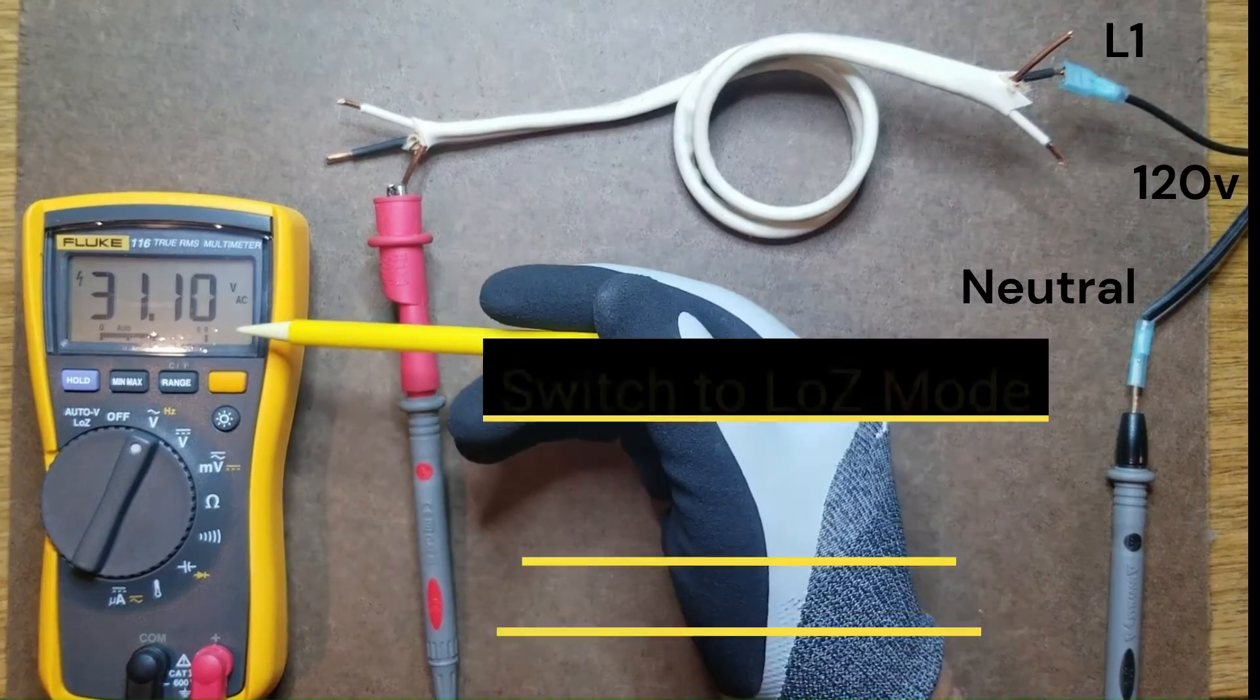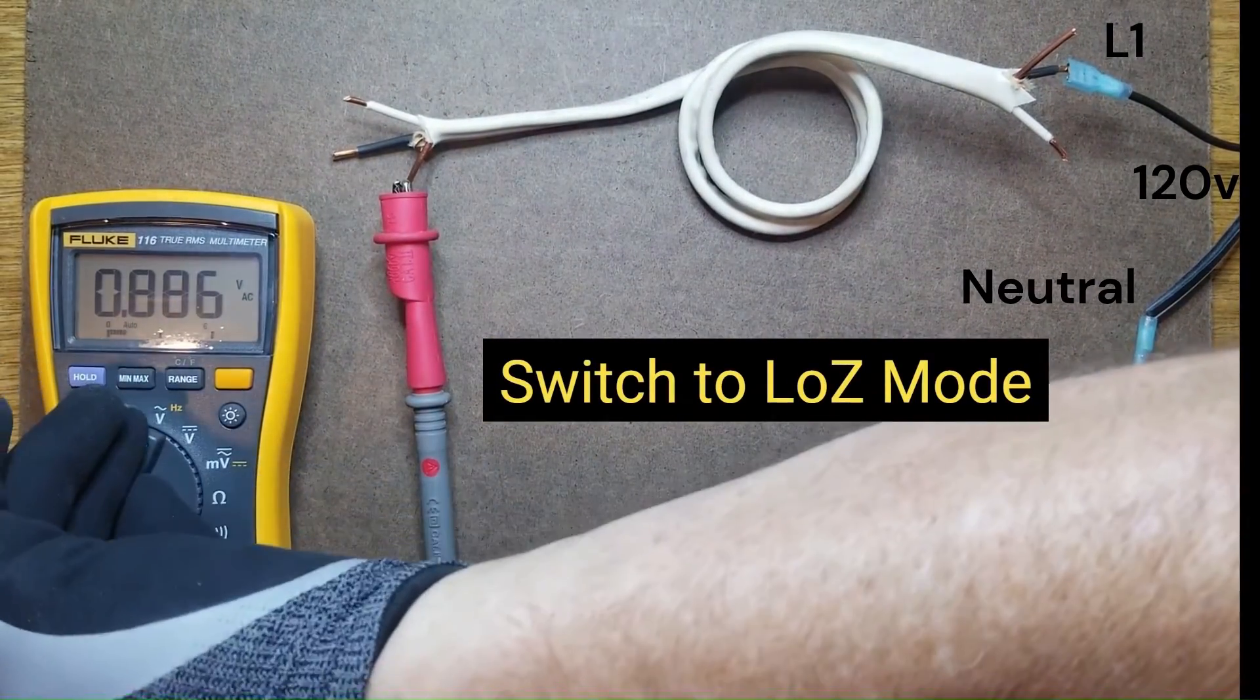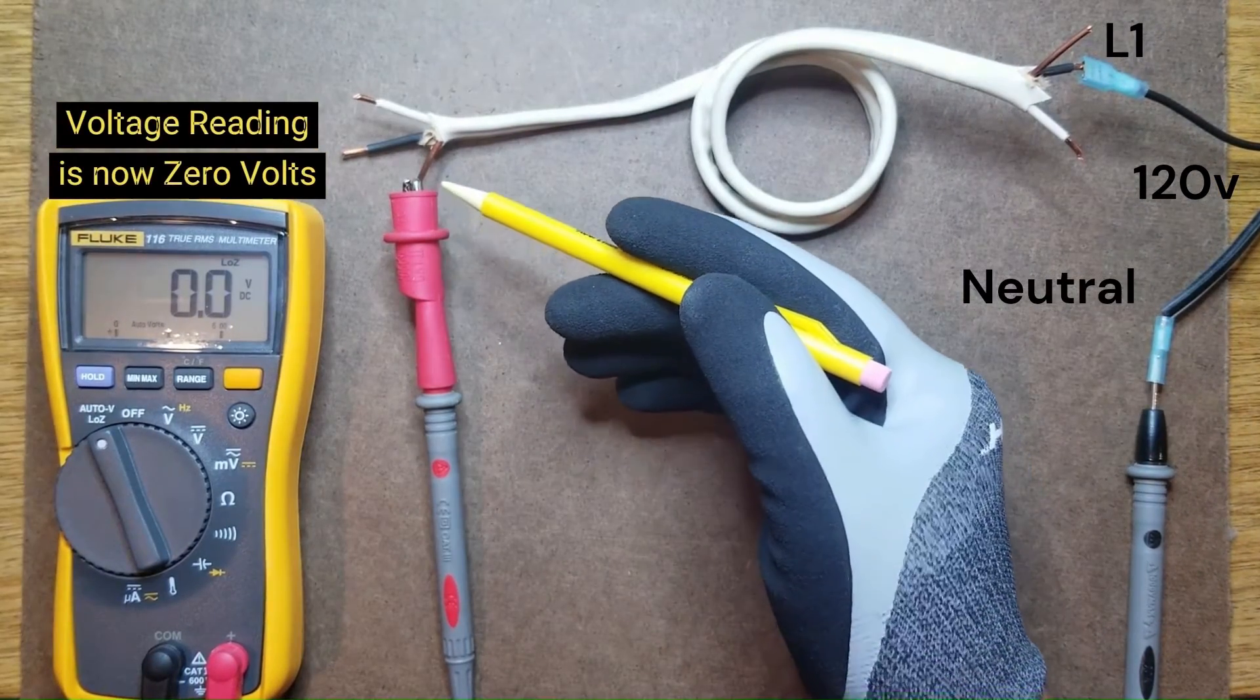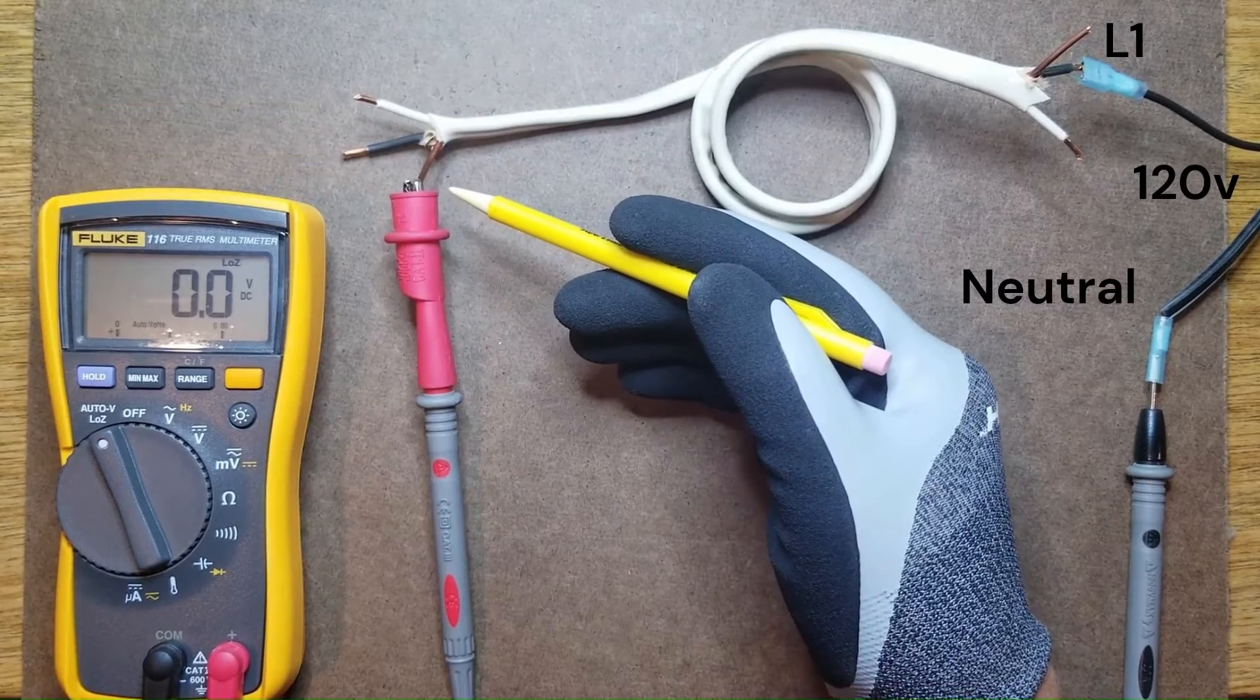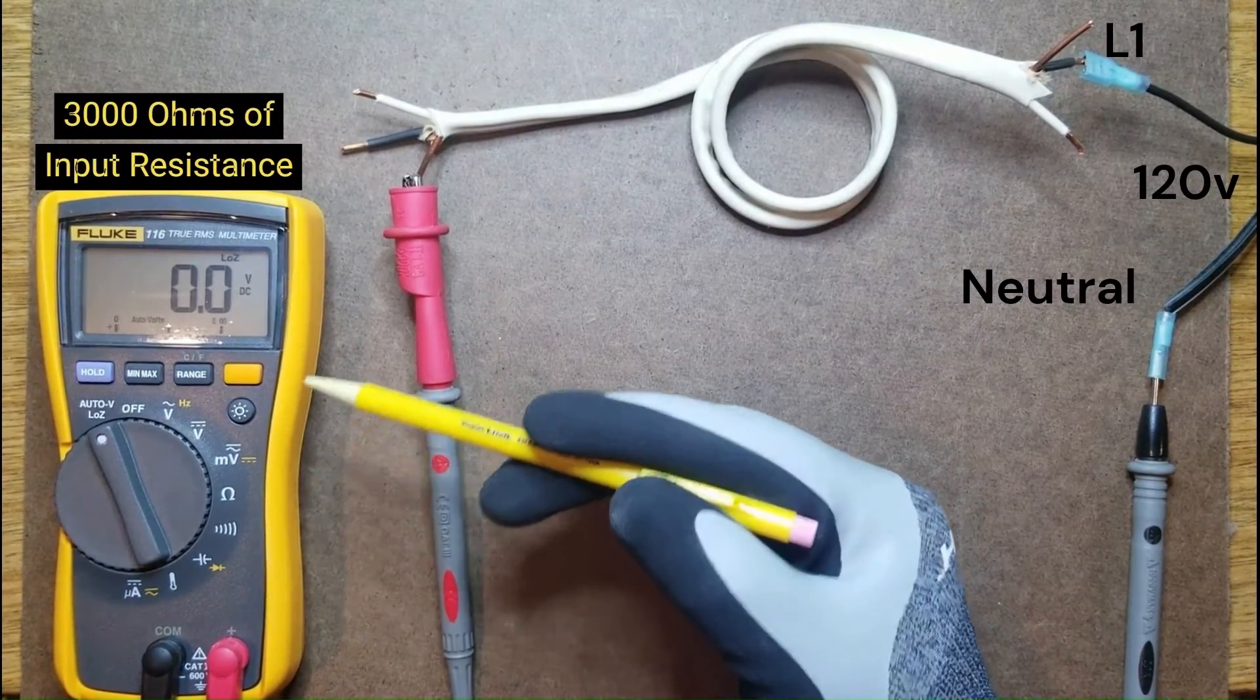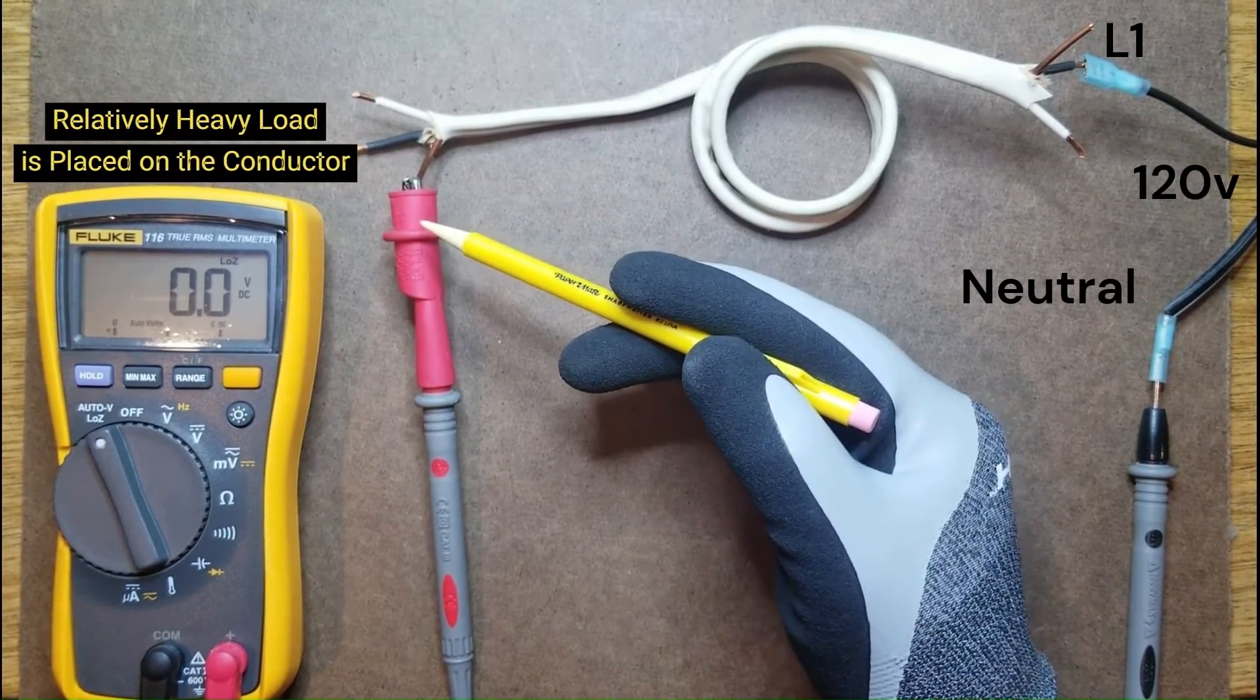Now if we switch to low Z mode, you'll notice that the voltage reading is now zero because we're using low Z mode which has an input resistance of just over 3000 ohms. A relatively heavy load is placed on the ghost voltage and it disappears.